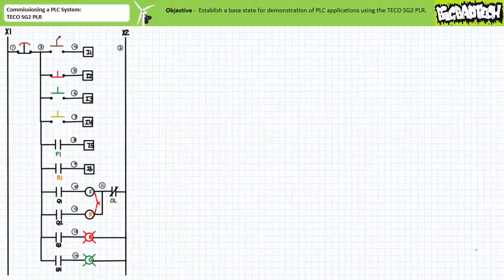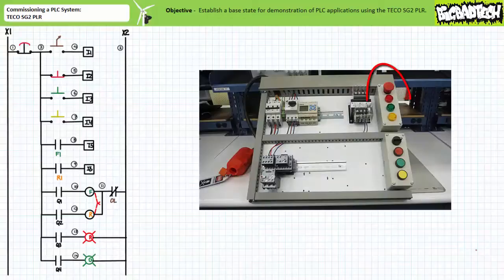Let's wire this system up. If we do this correctly the first time, always a dicey proposition given the involvement of your lazy lab partner, we theoretically should never have to do this again, and can quickly program and reprogram the PLC as we see fit to perform numerous different functions. First, install the e-stop and 3 pilot lamps, red, green, and yellow in the top push button enclosure. Note the yellow pilot lamp is a place filler and won't be used for this system. Its sole purpose is to prevent your lazy lab partner from sticking their finger in an empty hole.